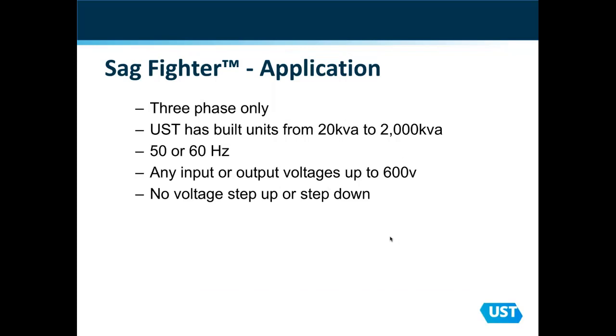Okay, sizes. We build this as a 3-phase only device. We've built up to 2000 kVA. We can build 50 or 60 hertz. And again, we're working with 600 volts or less. Because we're passing the voltage on through in standby mode, we do not have the opportunity to step up or step down the voltage.